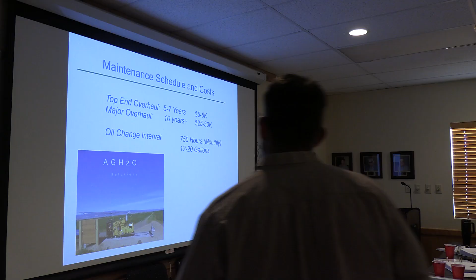Oil change interval when you're really going, it's got to be something like once a month, and be thinking of 12 to 20 gallons of oil when you make that oil change. So price that out. Obviously, you want to include plugs and what other items go with that. Some things that are critical components to the system when you're using a gen set.